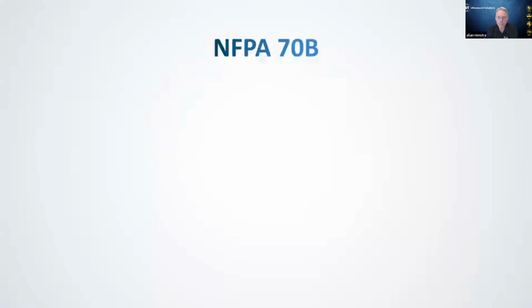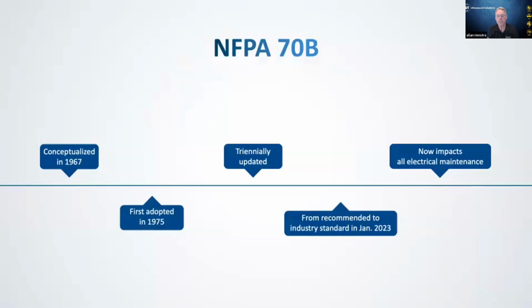But first, a history lesson. NFPA 70B has a long history as the guiding document for electrical maintenance practices, and it was first conceptualized in 1967. And officially in 1975, it became adopted as a standard. Since then, the standard's been updated on a regular 3-year cycle to keep pace with industry needs and safety requirements. The most significant change came just recently in January of 2023. Up until then, NFPA 70B was viewed primarily as a set of recommendations or best practices. But with the 2023 update, those recommendations transitioned into enforceable industry standards.